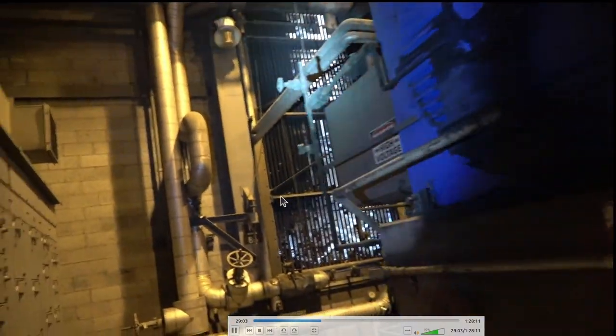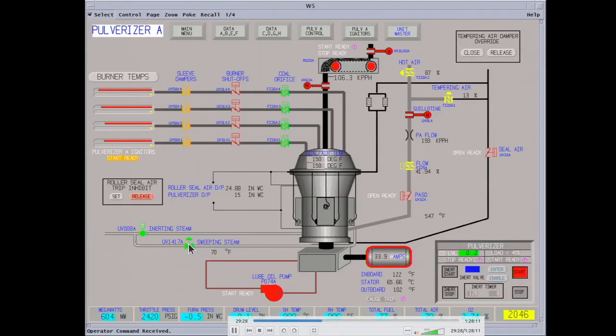Back here is the front of the air inlet heaters — this is where the air is heated coming in, using an oil solution for heating the air if we're near freezing. Here's the pulverizer on the north side. You have a lube oil pump that circulates the gear oil. There's an 800-horsepower motor driving the gearbox. You use inerting steam and sweeping steam for startups and shutdowns to inert the pulverizer and get rid of any combustion. If you have any smoldering coal, you'll put it out. Hot air comes in and is mixed with your tempering air — this temperature is trying to maintain 150 degrees on this unit.